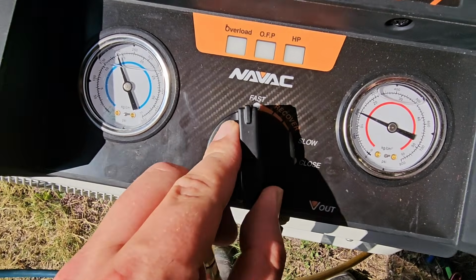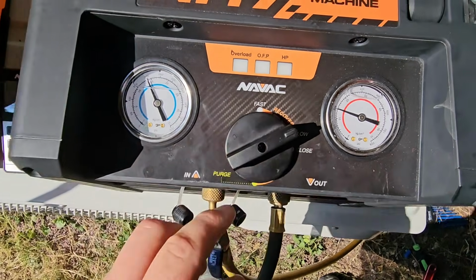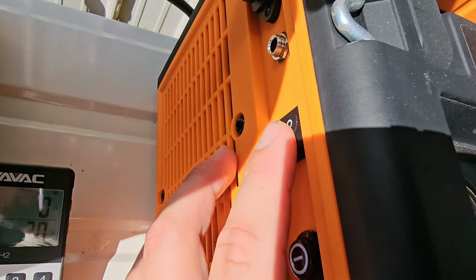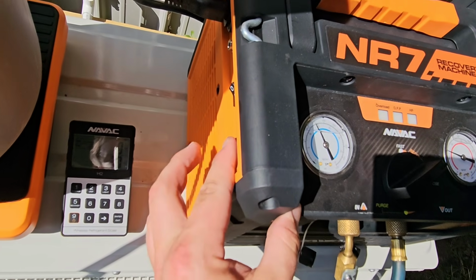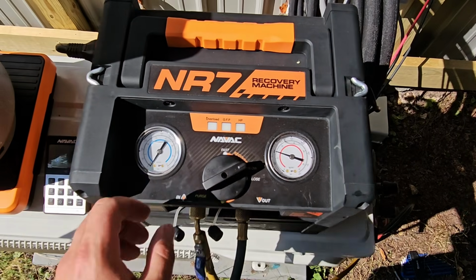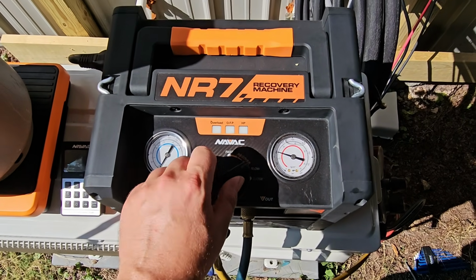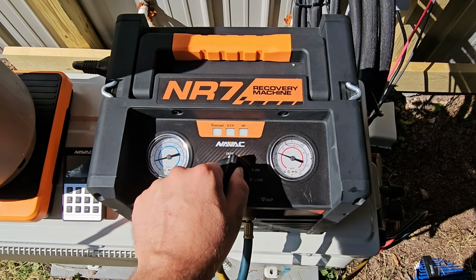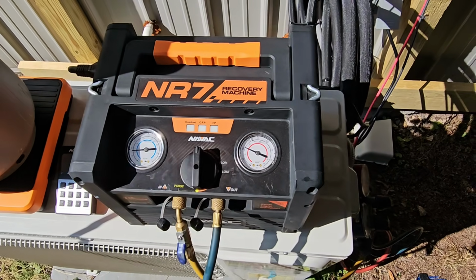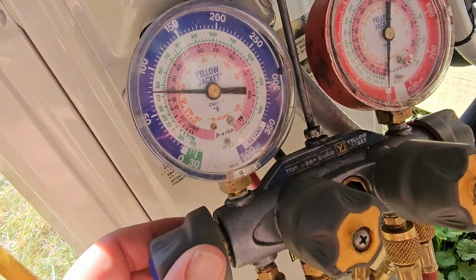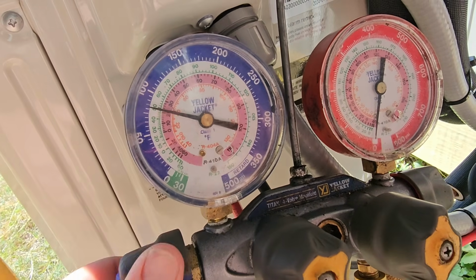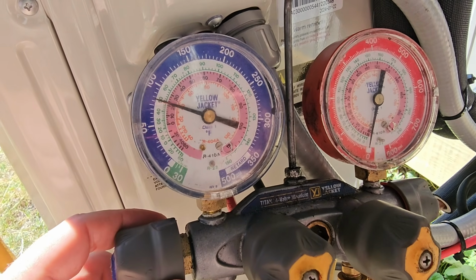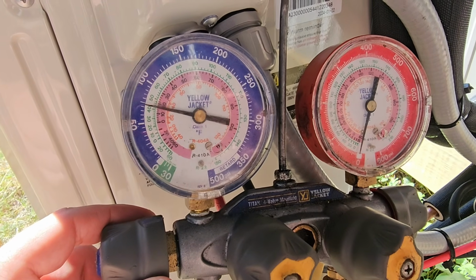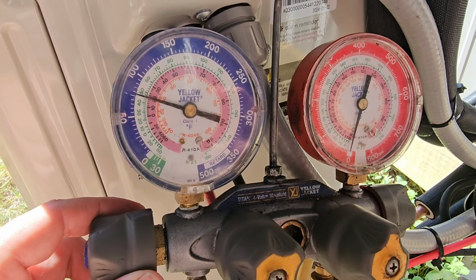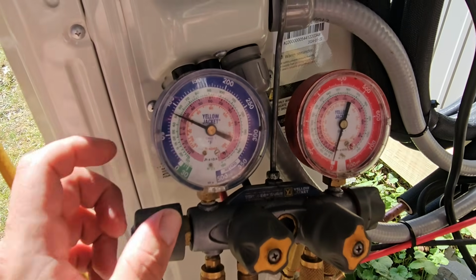We're going to bring this back to where it says slow, and then we're going to turn on the switch. Pa-ching. Push this button. And there it goes. And you can adjust the speed up and down. Whoa, look at that. It's pulling that refrigerant out. Let's let this run for a minute.